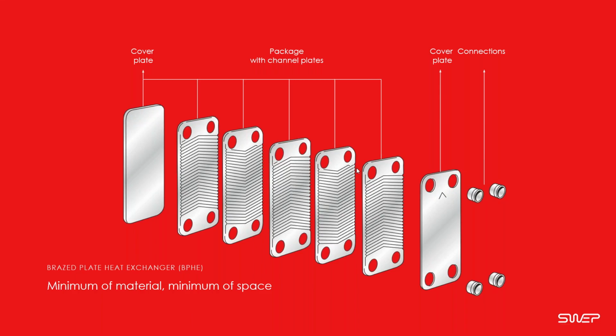We then have the front and back cover plates. These provide additional support and stability. So for applications where there's vibration and stress, it gives mechanical strength to the heat exchanger. We then have the connections as well, which we'll cover a little bit more in detail later. Generally, these are fitted to the front of the heat exchanger. However, depending upon the heat exchanger type or indeed the application and customer preference, we could, for example, have 2 connections here on the front and also 2 on the back.